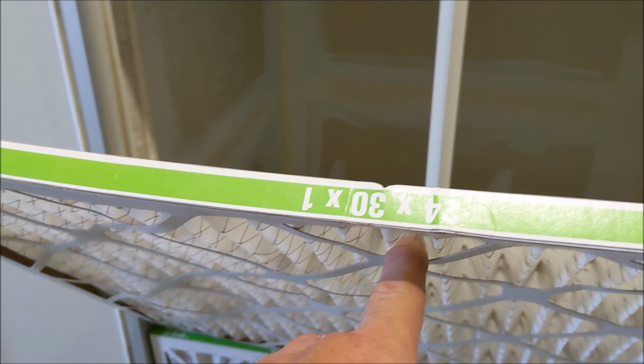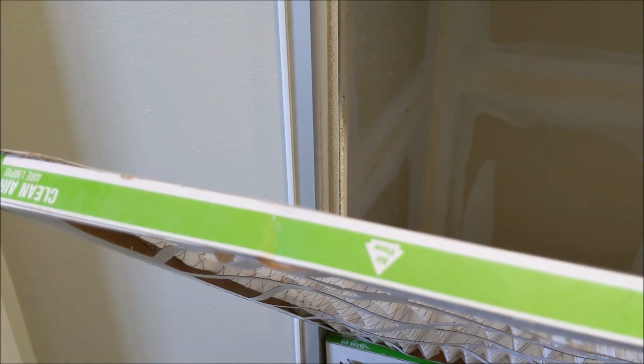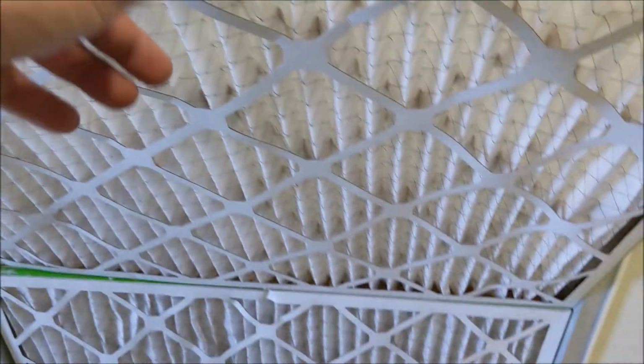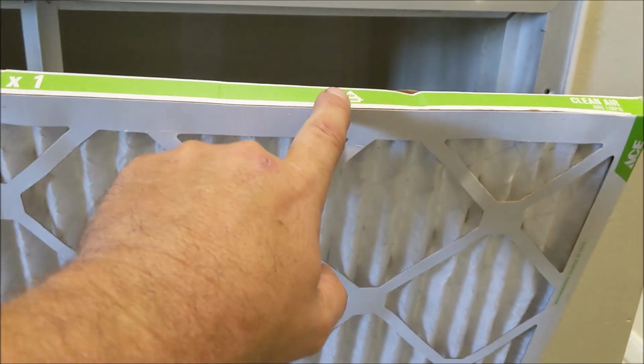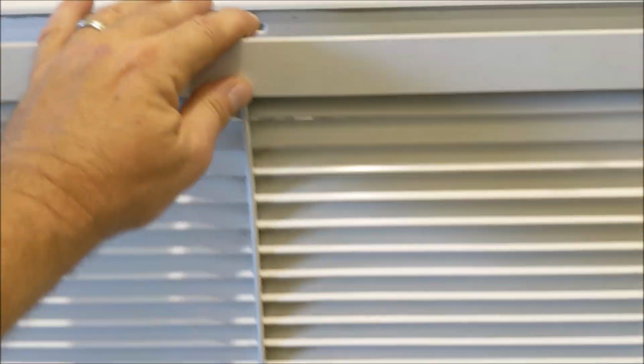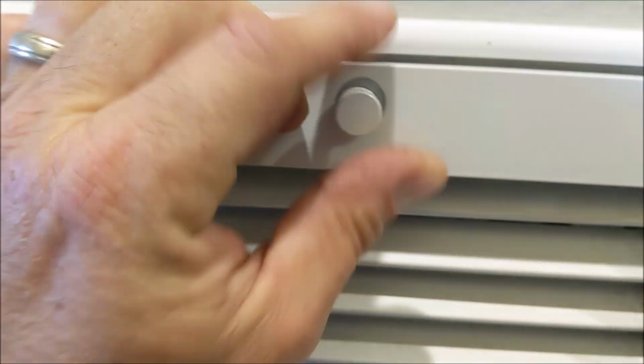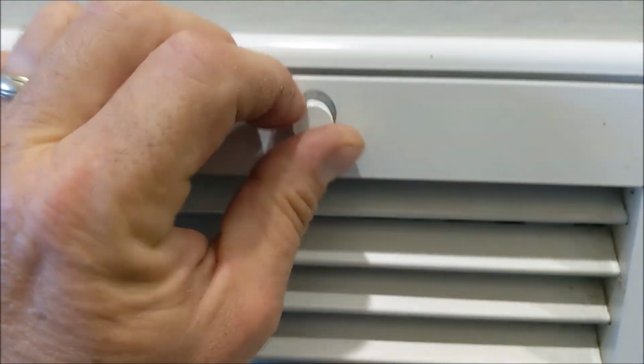This is the air filter, 24 by 30. As you can see, the arrow is facing the wrong way for the air return. This is the one that's a dual. Basically the air filters go this way, because which way is the air being sucked? This way. So which way should the arrow go? Airflow this way. Alright, so flip those air filters around and you should be good.